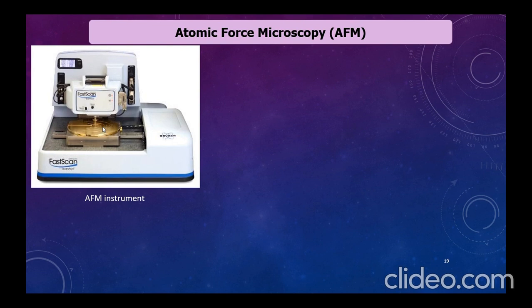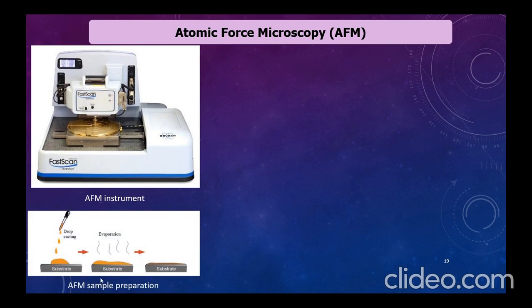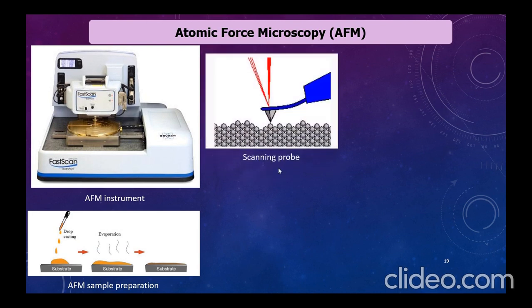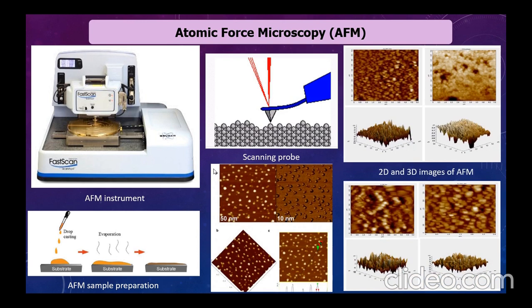AFM (atomic force microscopy) provides high-resolution topographical and surface property information by scanning a sharp probe over the sample surface while measuring forces between the probe and sample. A tip attached to a cantilever moves up and down in response to attractive or repulsive forces with the sample surface, and the cantilever movement is detected by a laser and photodetector. AFM provides 2D and 3D topographical images and can measure local mechanical properties such as stiffness, elasticity, and adhesion forces.